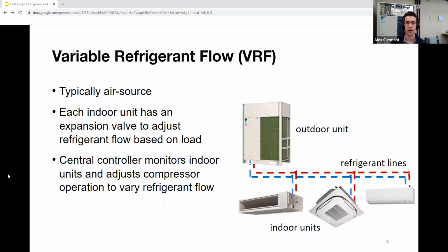Now, this is perhaps Jason and I's favorite topic, but now we're looking at one of the most common commercial air source heat pumps, which is VRF, for variable refrigerant flow. With these, every indoor unit has an expansion valve and can modulate how much refrigerant it wants based on the load. And the outdoor unit will in turn modulate the amount of the compressor to adjust for the amount of refrigerant needed in real time for each indoor unit, and hence the name VRF.